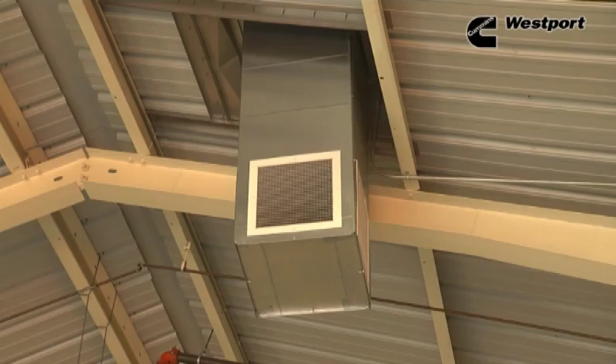Natural gas is lighter than air, so considerations about proper roof height and ventilation are important. Gable or open web steel joist roofs are well suited for your facility, as gas will not pocket and ventilation systems can be modified. The air handling system will circulate and evacuate air within the shop to prevent accumulation of methane. Also, all electrical service should be relocated to at least 18 inches below the ceiling. The ceiling height should be sufficient so that any leaked gas can rise above potential ignition sources, with a height above 20 feet being best.